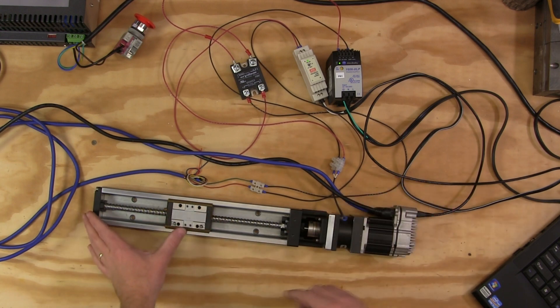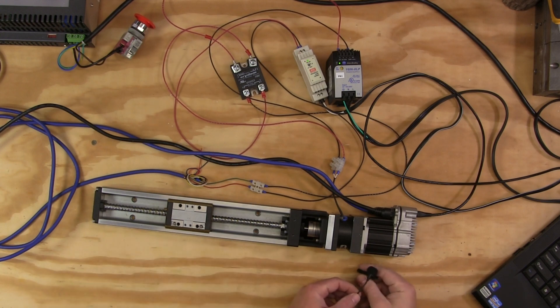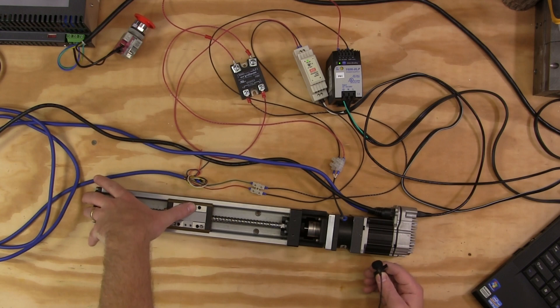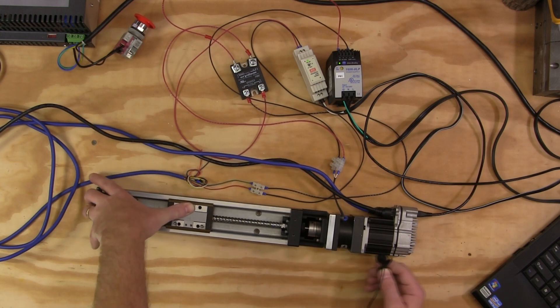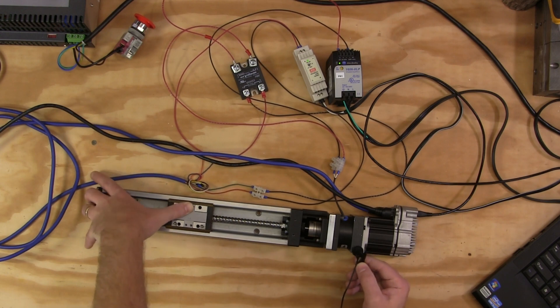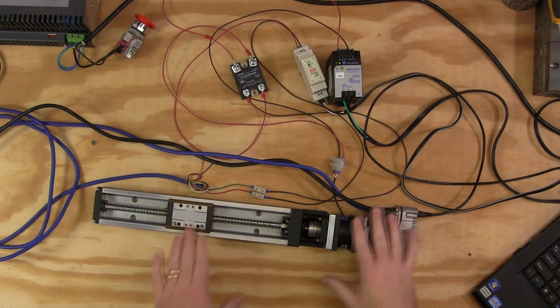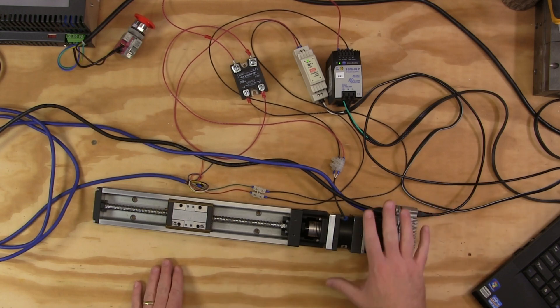If you can see that on the servo motor, that means it's happy and enabled. So brake release, motor enabled. Now the motor is holding the load and I don't know that you'll be able to hear this. I'm going to sit the mic down here just for a second. See if you can hear the motor kind of creaking. And that's it kind of fighting against me or pushing against me because it's wanting to maintain the position of the truck on the ball screw now because it's not being told to move.